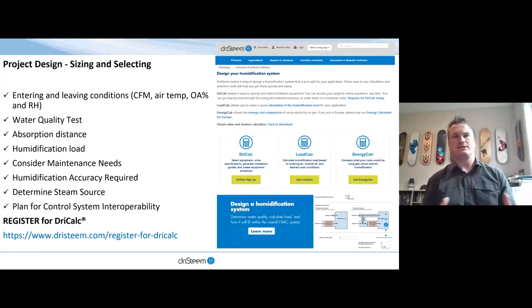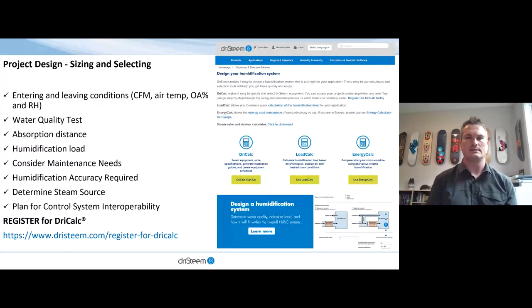So when we look at the project design and the sizing and selection, what are the tools out there and what are the things that we like to look at or need to know in order to size and select and lay out a project appropriately? The entering and leaving conditions, the volume of air, the air temp, the percentage of outside air is very important, which I'll show in the next slide, and what that relative humidity is coming in. If we're in Miami, Florida, it's going to be very different than if we're in Tucson, Arizona, for example.